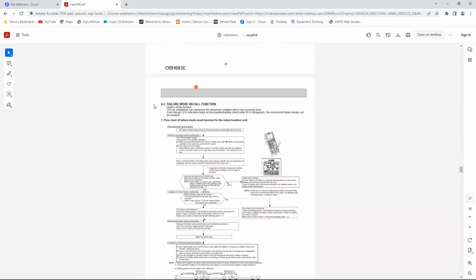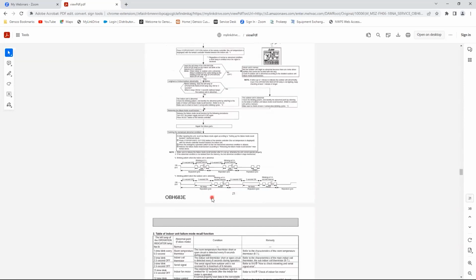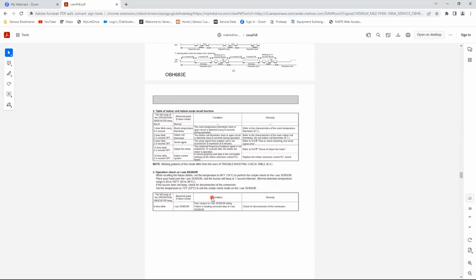It talks about failure recall mode. A homeowner had a problem over the weekend. They reset power, so the error is no longer being displayed. They called you out to see what was going on. At that point in time, you would use failure recall mode, because the indoor unit stores the last error code in it. So you perform the failure recall function, which is laid out right here and walks you through it step by step.